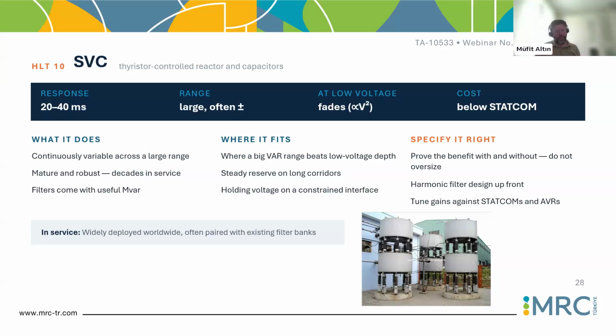Right now, as Mevlüt also mentioned, you are starting with static studies, load flows, short circuit, and afterwards RMS studies. But for these kinds of SVCs, STATCOMs, and grid forming issues, you have to model the EMT models of the equipment, and then you can design by looking at the harmonics and other issues in your system. Then you will be sure that this is my requirement and this is my solution. Next slide.